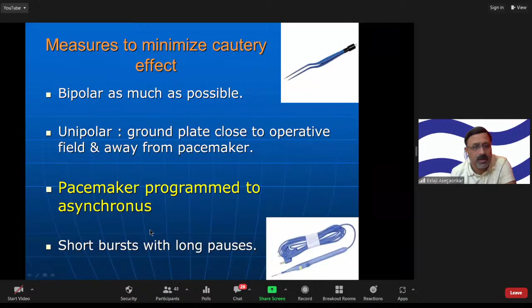Initially, when you start using cautery, always check with a short burst whether it is causing pauses, whether it is interfering with the mechanical function of the heart. Then and only then should you start using cautery. One has to be extremely careful. Avoid use of cautery within 15 centimeters of the pacemaker. These are for unipolar. And nowadays, we are maximally using bipolar cauteries. A temporary pacemaker should always be kept ready. In any mishap, if the pacemaker is not functioning, how will you increase the heart rate of the patient? Drugs like isoprenaline and atropine should be kept ready, but they may not be effective. So a temporary pacemaker must always be kept ready.